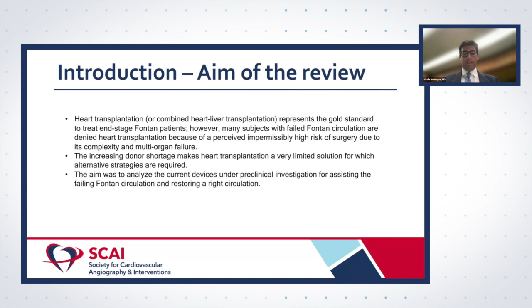The first in vitro study analyzing a preclinical device was an intravascular axial flow blood pump, the figure on the left, a collapsible device for percutaneous positioning in the IVC and/or in the superior vena cava. Its in vitro performance was 2 up to 6 liters per minute with a rotational speed of 6,000 to 10,000 RPM, generating a pressure rise inside the Fontan circuit of up to 20 millimeters of mercury. The design showed very favorable hemolysis. This was tested both in an idealized Fontan and in a real anatomical patient-based model created with 3D reconstructions, and it was found to produce higher pressures with a low effect of blood viscosity on function and a low probability of blood damage.